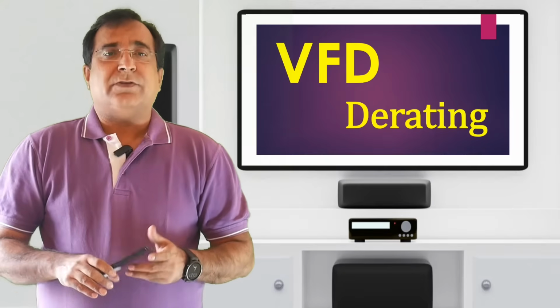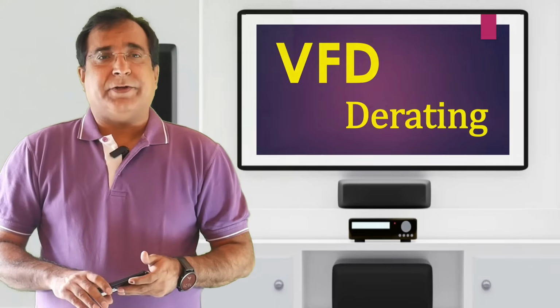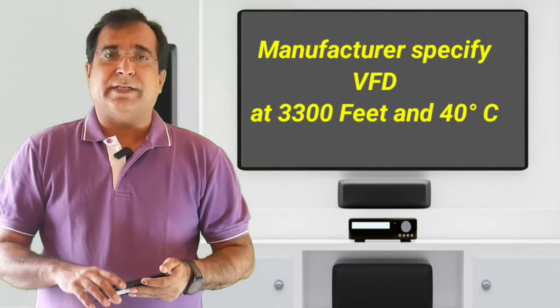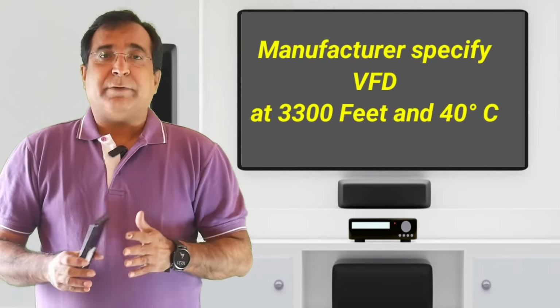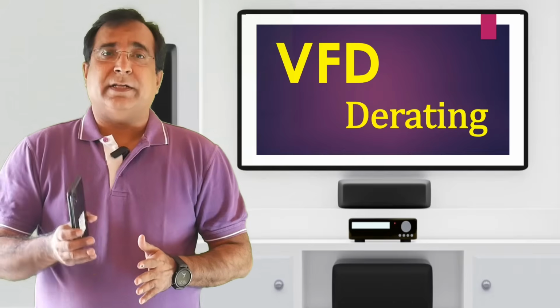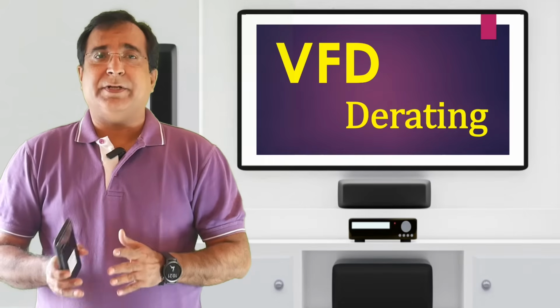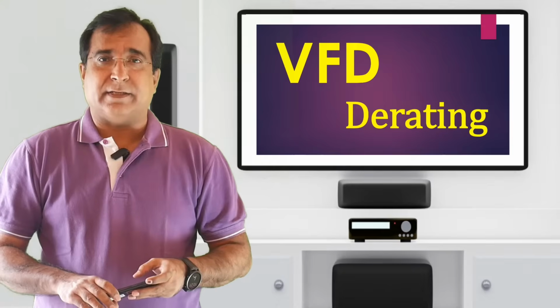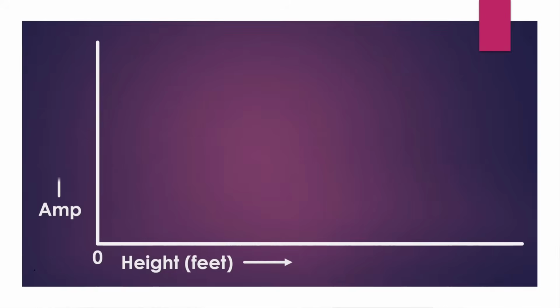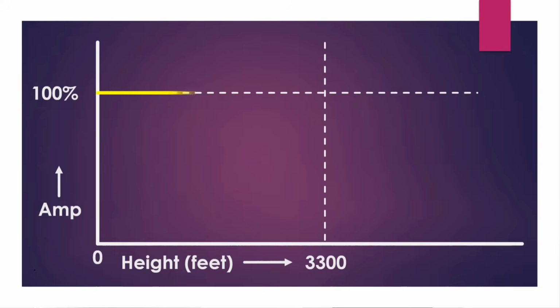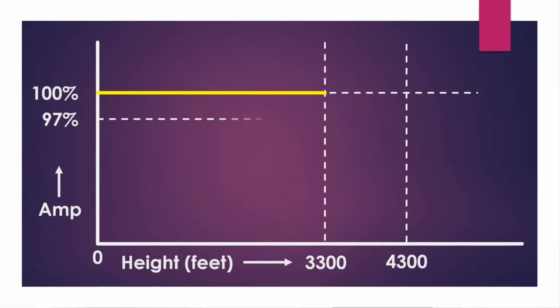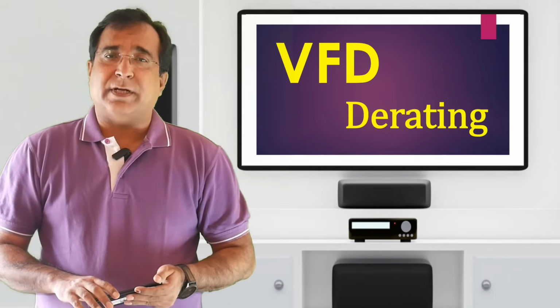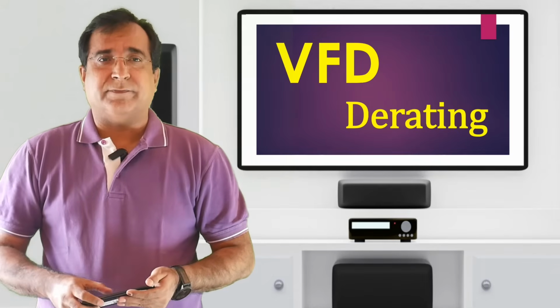Clear? That's why manufacturers specify the VFD at an altitude of 3300 feet and 40 degrees Celsius ambient temperature. That means if the VFD is operated within 3300 feet above the sea level and the ambient temperature within 40 degrees Celsius, then the VFD does not derate its current capacity. So you are safe till 3300 feet and 40 degrees Celsius temperature. VFD will derate its current capacity by 3% for every further 1000 feet above 3300 feet, and derate by 1% per degree Celsius above 40 degrees Celsius.